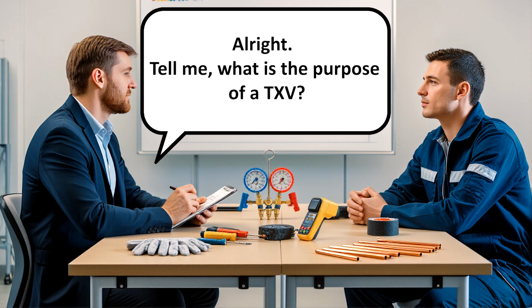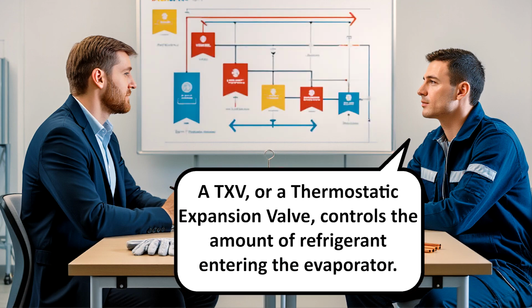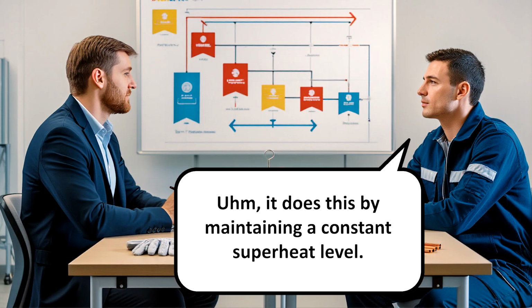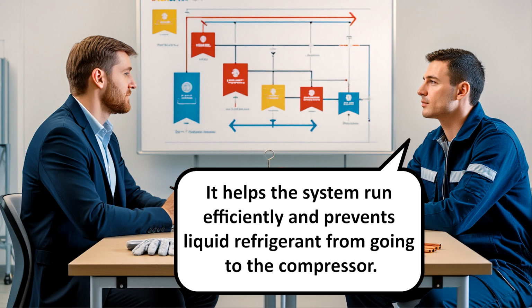All right, tell me, what is the purpose of a TXV? A TXV, or a thermostatic expansion valve, controls the amount of refrigerant entering the evaporator. It does this by maintaining a constant superheat level. It helps the system run efficiently and prevents liquid refrigerant from going to the compressor.